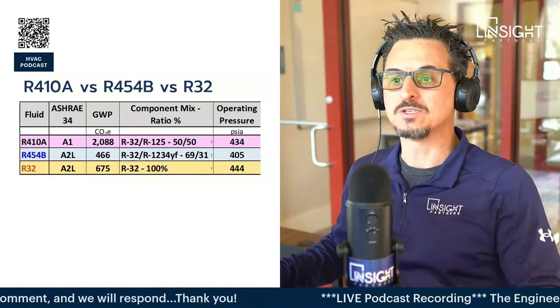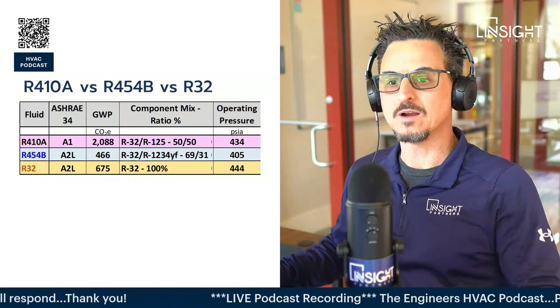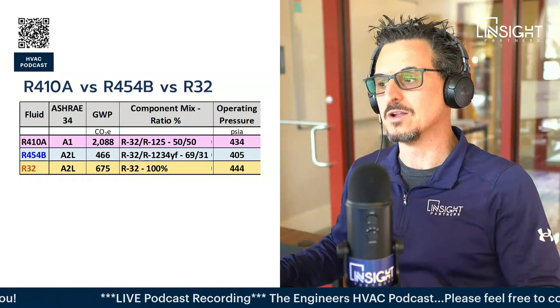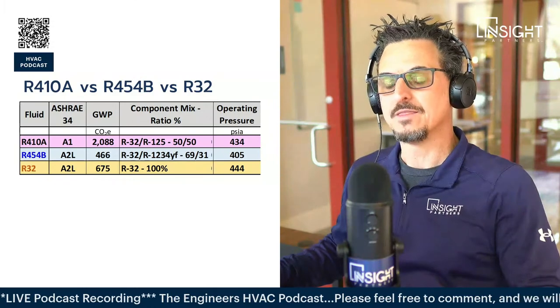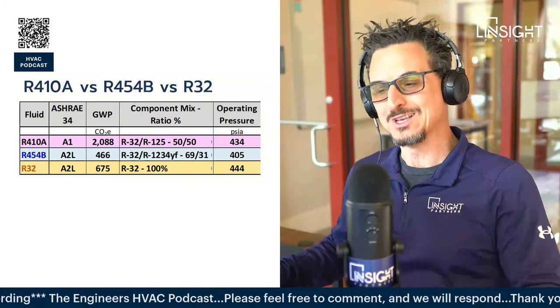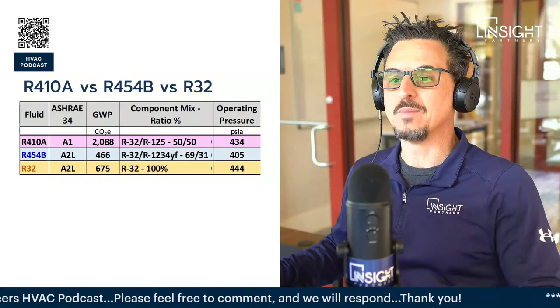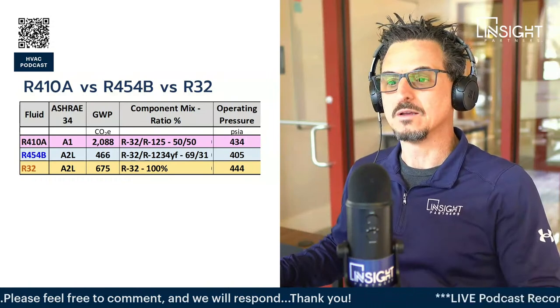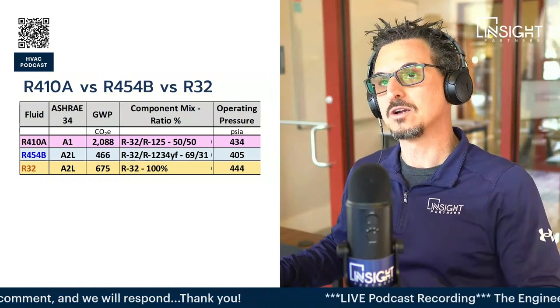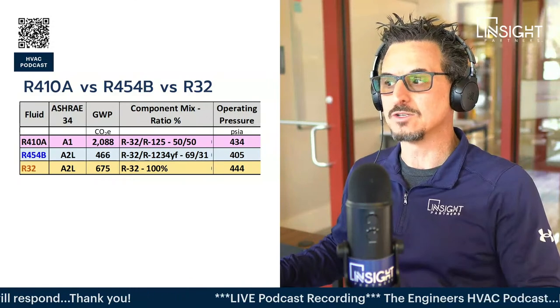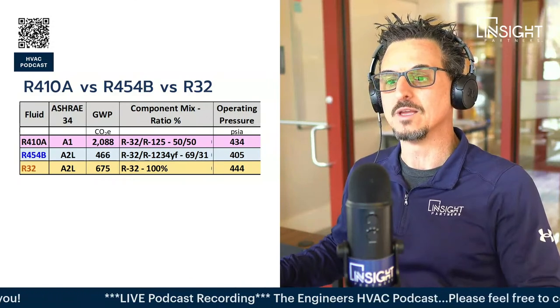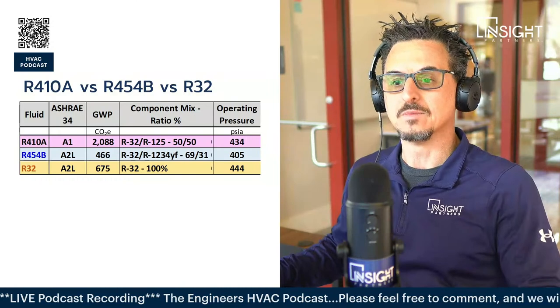It's important to note that R410A and 454B are what's called near azeotropes, which means they don't have a lot of temperature glide - they maintain this ratio pretty closely whatever state they're in. So you can currently charge 410A up to 10% of the unit charge without having to evacuate the system and redo it. A little bit to note there.